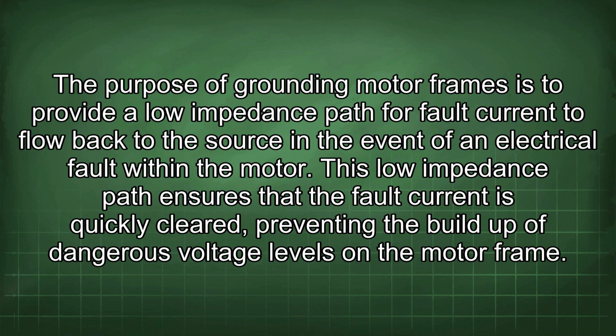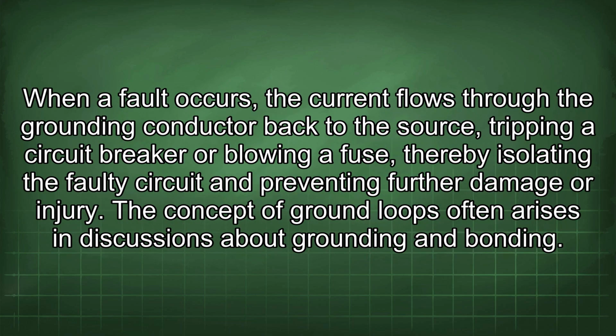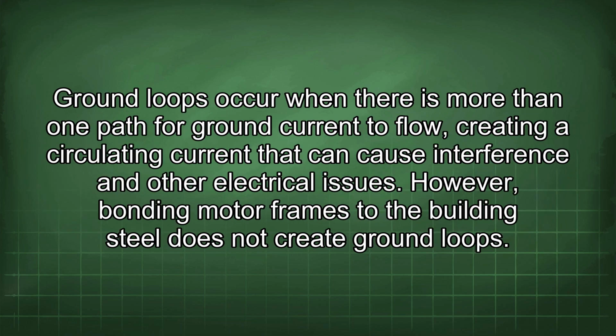This low-impedance path ensures that the fault current is quickly cleared, preventing the build-up of dangerous voltage levels on the motor frame. When a fault occurs, the current flows through the grounding conductor back to the source, tripping a circuit breaker or blowing a fuse, thereby isolating the faulty circuit and preventing further damage or injury. The concept of ground loops often arises in discussions about grounding and bonding. Ground loops occur when there is more than one path for ground current to flow, creating a circulating current that can cause interference and other electrical issues.